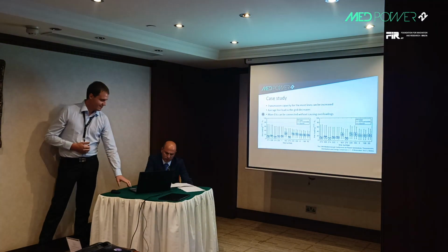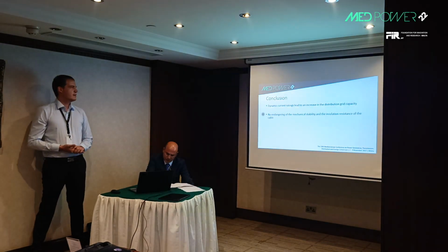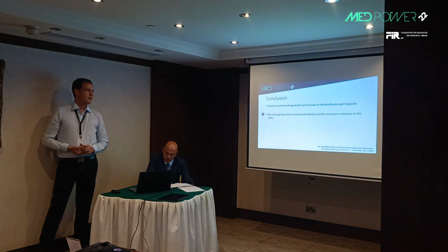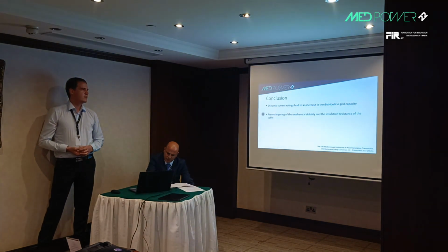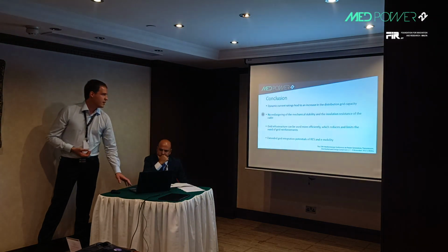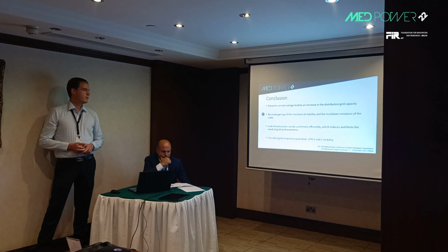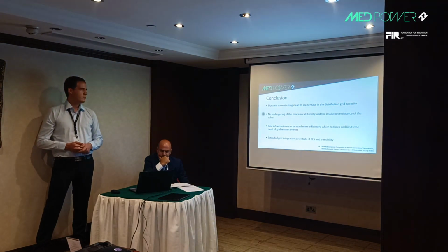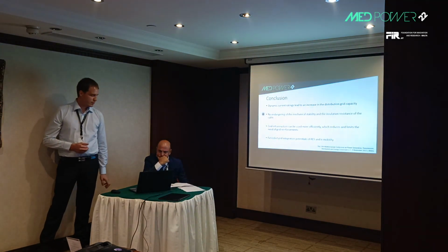And the conclusion is that the dynamic current ratings lead to increased distribution capacity without endangering the mechanical stability and the insulation resistance of the cable. And the grid infrastructure can be used more efficiently with reduced and limited need of grid reinforcements. And we have extended grid integration potential for RES and e-mobility.